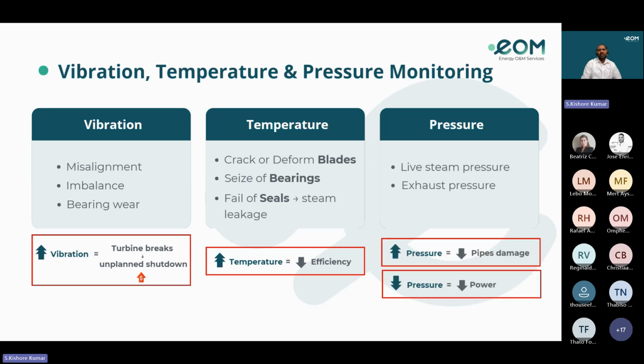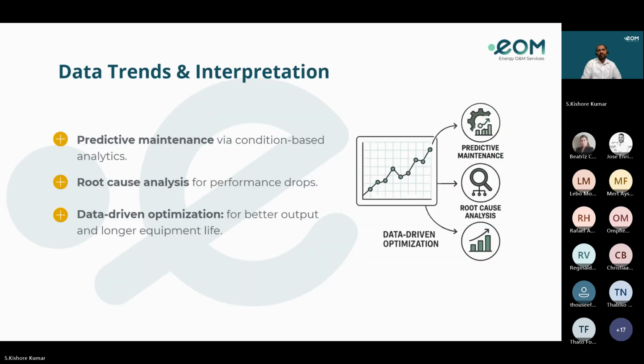Stable steam pressure means steady and efficient turbine operation. If it is too high, there is a risk of damage to pipes or equipment. If it is too low, the turbine won't produce enough power. So in data trends and interpretation, harnessing the power of historical and real-time data and trends allows predictive maintenance via condition-based analytics, root cause analysis (RCA) for performance drops, and data-driven optimization for better output and longer equipment life.